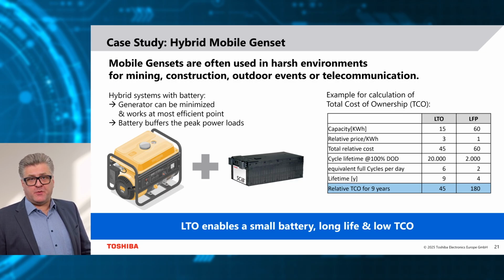Comparing LTO with, for example, LFP batteries for such an application, a significant difference lies in the service life and the costs. LTO batteries are characterized by a significantly longer service life. LTO offers up to 20,000 charging cycles compared to the approximately 2,000 charging cycles of LFP batteries. This higher number of cycles means that LTO batteries are more reliable and sustainable in the long term. However, these advantages are reflected in higher acquisition costs. Despite this higher initial investment, a comparison of the total costs of ownership, TCO, over 9 years shows that LTO with a TCO of 45 is more economical overall than LFP with a TCO of 180, where you have to replace the battery every 4 years.